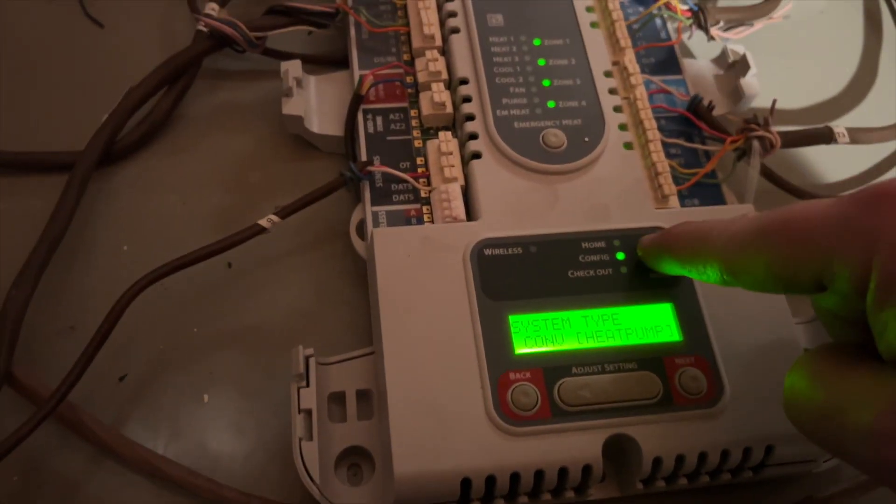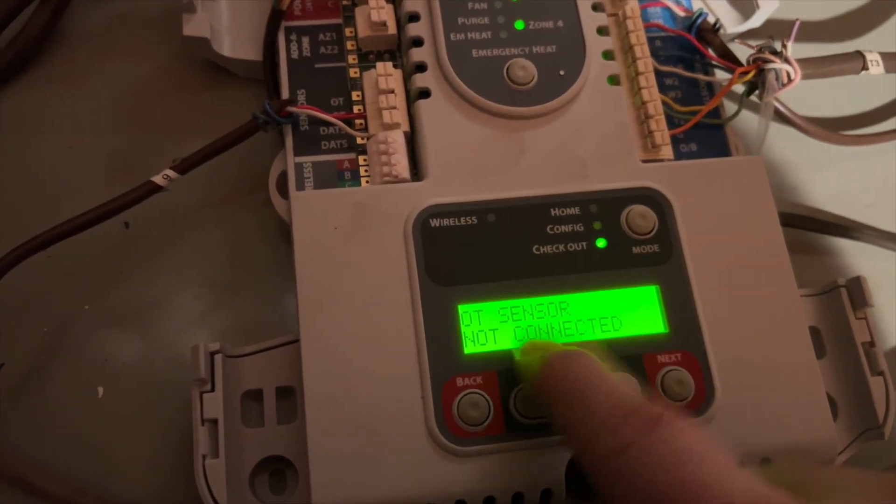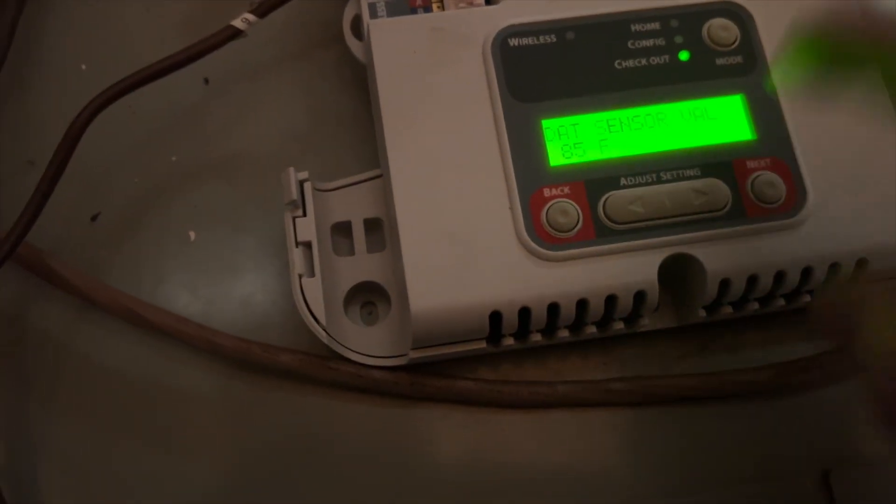So if we hit mode again, we hit it one more time, this takes us into checkout. Now checkout mode will allow us to turn things on. Now if this had an outdoor temperature sensor, it would show the temperature there, but we don't have one, so that's why it's saying it's not connected. If we hit next, this is our discharge air temperature sensor. It's reading about 85 degrees right now. That's because the heat was just running.